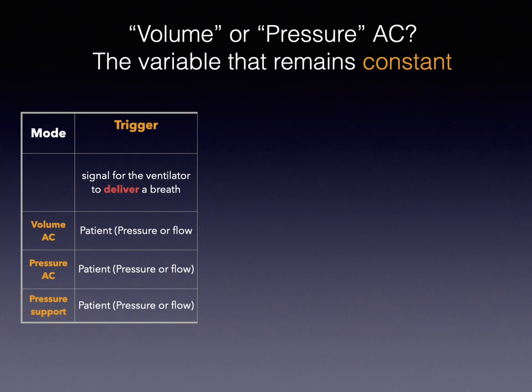The first thing the machine needs to know is when the patient wants to initiate the breath — that's called the trigger. The patient needs to trigger the breath, the machine detects that signal knowing the patient is initiating the breath, and the inspiration cycle begins. The machine can detect whether the patient makes a negative pressure or reaches a certain inspiratory flow, so that the machine knows the human is trying to take a breath.